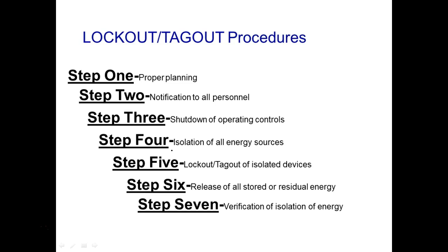Isolate all energy sources—it doesn't say just electric, it says all energy sources. Lockout, tagout of isolated devices, release all stored energy or residual energy, which usually comes with a hydraulic or pneumatic system. But it could also be something lifted up in the air—that would also be stored energy. You might need to lower it down before you kill power if you can.